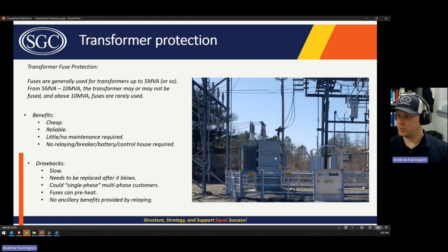Transformer fuses. This is a picture of a transformer at a substation. This one feeds my house, so I was jogging by there and was able to get this picture. Fuses have some advantages. They're cheap, they're reliable. There's little to no maintenance required. There's no relaying, battery, or control house required. The drawbacks are that they're slow. They need to be replaced after they operate. You can single phase customers.